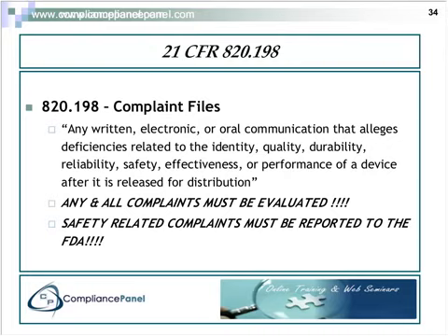You must have a very stringent procedure in place on how these are evaluated and investigated. Any safety-related complaints, where there was a direct injury or death or the possibility of an injury or death, must be properly documented and relayed to the FDA in specific time frames. In other parts of 21 CFR 800, there are specific details on how these have to be reported.